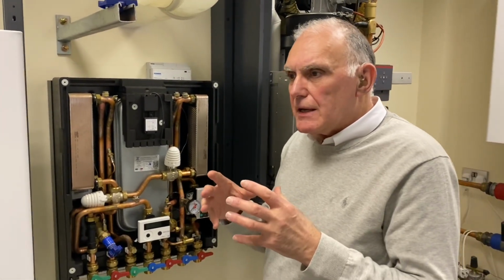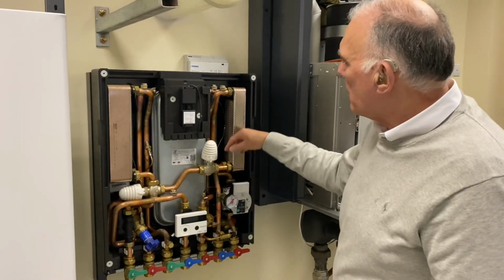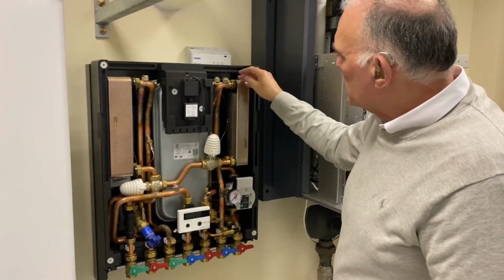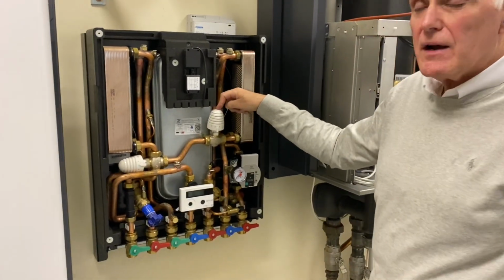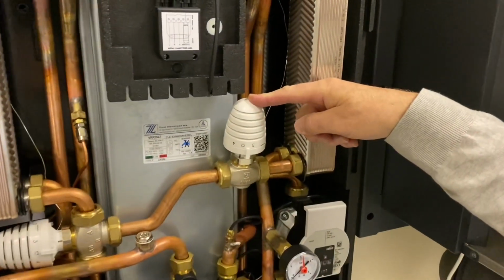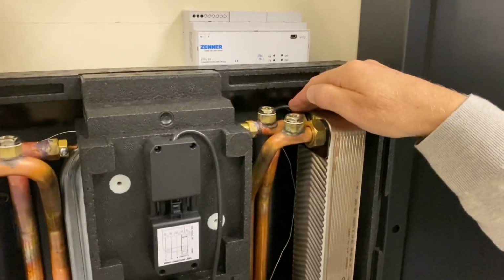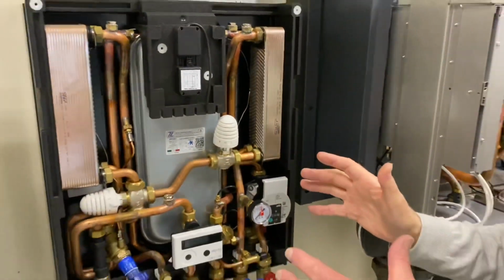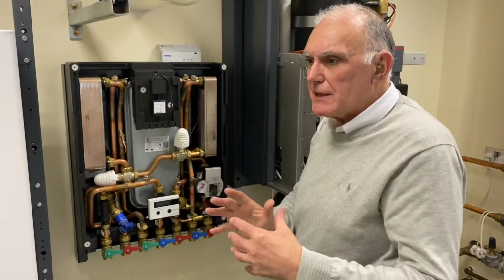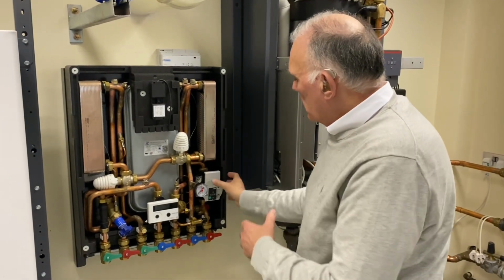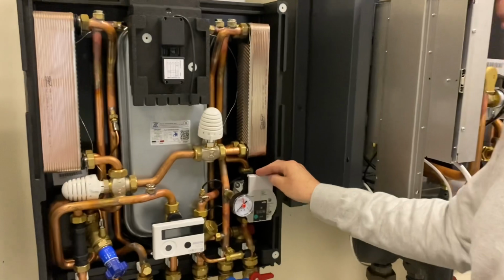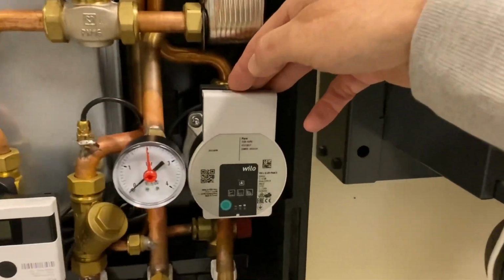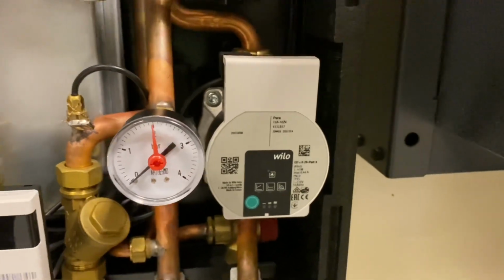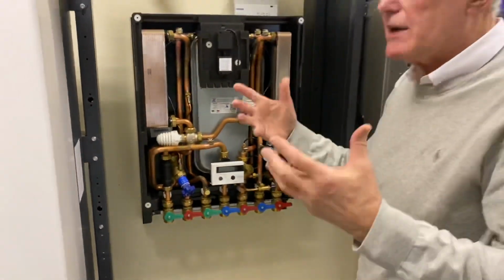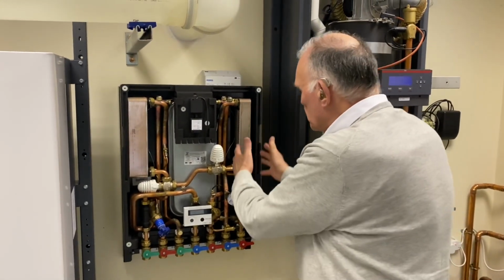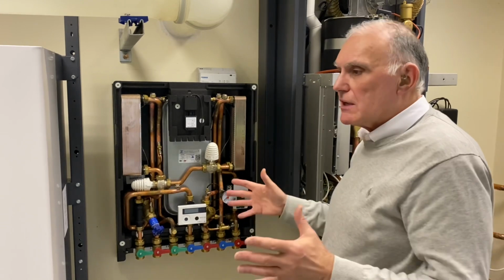The central heating is controlled in a very similar manner. So primary flow in, the temperature of the space heating is controlled by a control here, sensor located at the back at the top, and so that would be the control of the temperature of the water to the space heating system. The pump for the space heating system is here, and we can incorporate mixing valves, motorized valves, blending valves, a room thermostat, a modulating thermostat, weather compensation to control the output into the space heating, whether it's underfloor or radiators.